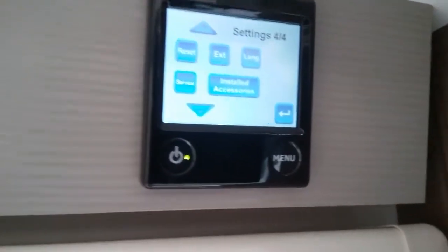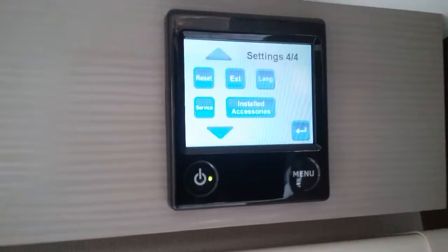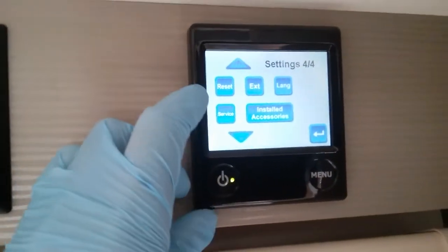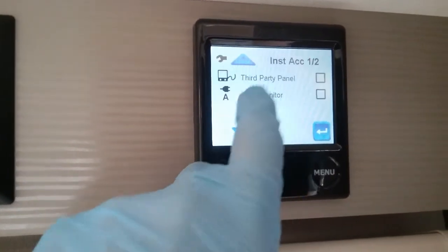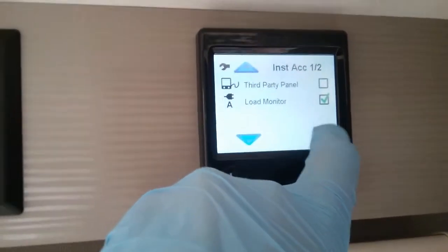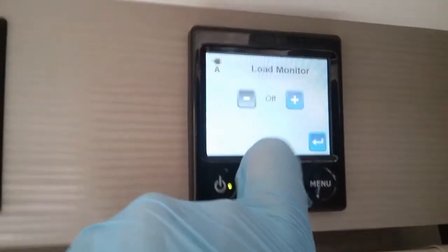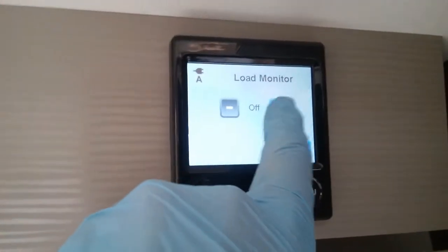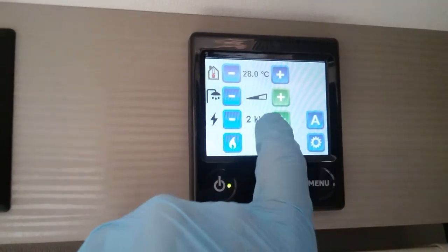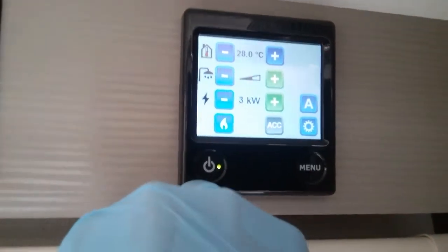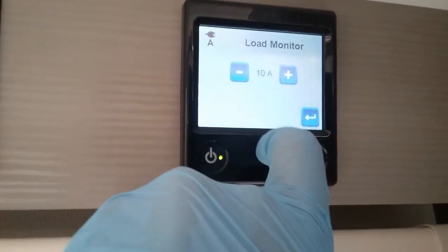External start — you do have to have an iNet box fitted if you want to control the heating and hot water via an app. We then have language, and service which is more for the workshop but will let you know what everything is up to. Installed accessories — the only one that's really handy in here is the load monitor. If I tick that and go back up you'll see we can access it now. So if you arrive on site and you know how many amps it is you can select it on here, and because I've now selected 10 amps the system will not use three kilowatts — it will avoid tripping.